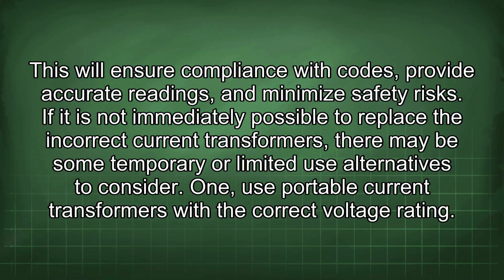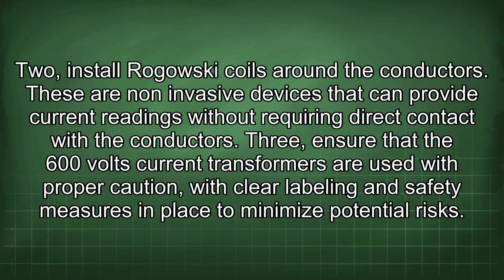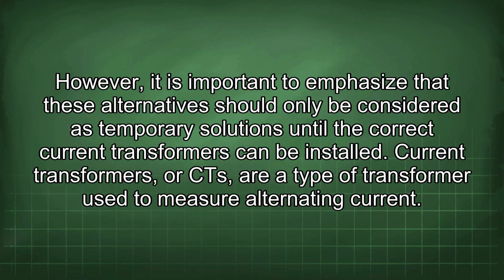If it is not immediately possible to replace the incorrect current transformers, there may be some temporary or limited use alternatives to consider. 1. Use portable current transformers with the correct voltage rating. 2. Install Rogowski coils around the conductors. These are non-invasive devices that can provide current readings without requiring direct contact with the conductors. 3. Ensure that the 600 volts current transformers are used with proper caution, with clear labeling and safety measures in place to minimize potential risks. However, it is important to emphasize that these alternatives should only be considered as temporary solutions until the correct current transformers can be installed. Current transformers, or CTs, are a type of transformer used to measure alternating current.